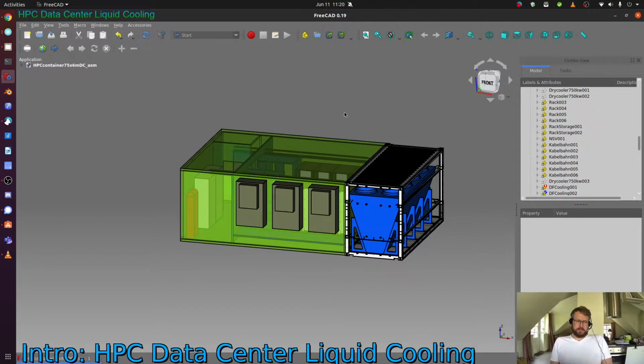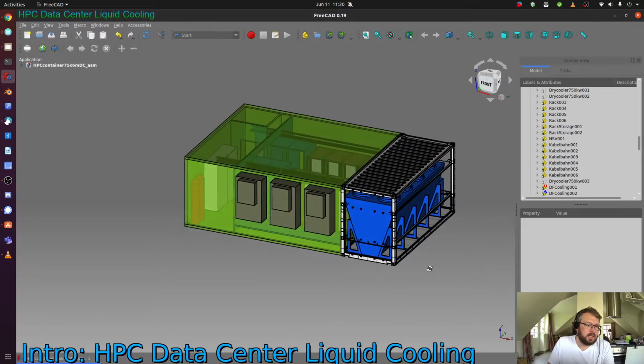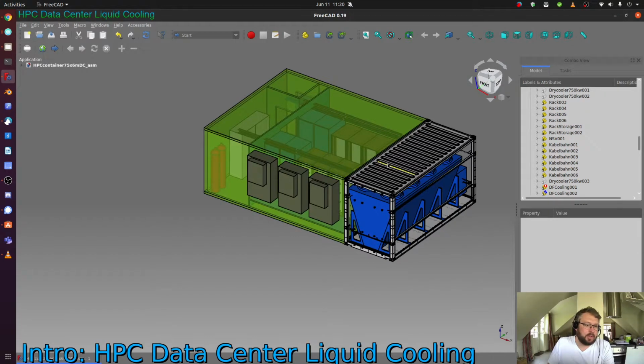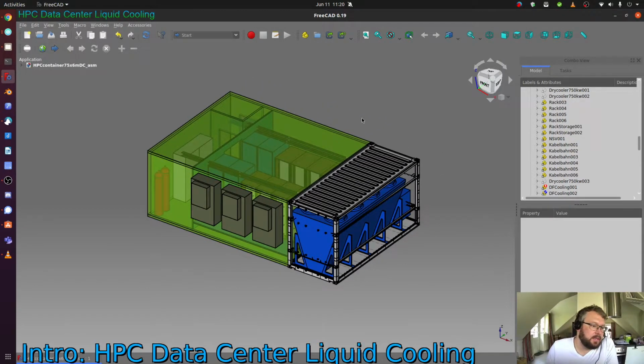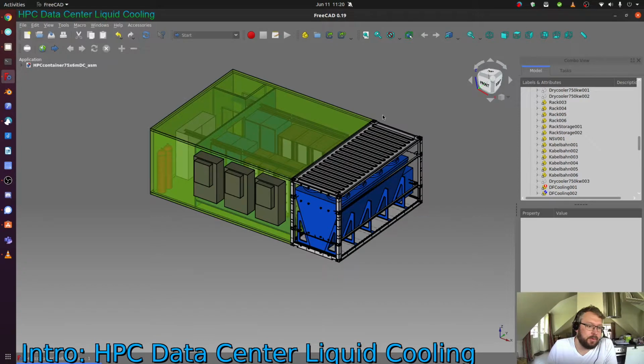Let me talk you through some of the features on the outside, and then go into the inside arrangement. So the space requirements were quite limited. This is why this looks like such a compact form factor. These are 4 20-foot ISO containers, 3 of them joined together here as the white space for the IT, and the 4th container is actually holding the dry cooler, a large massive dry cooler.